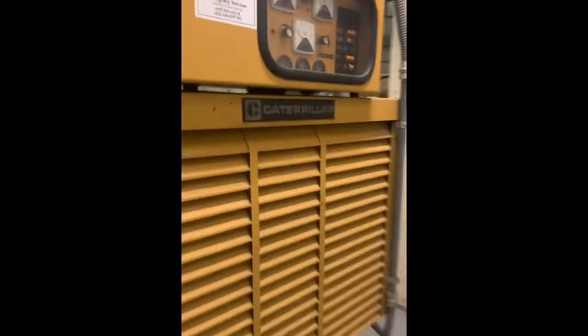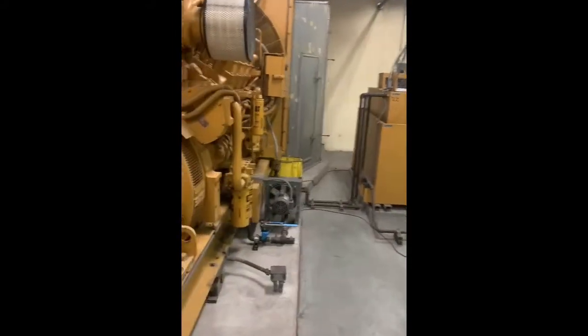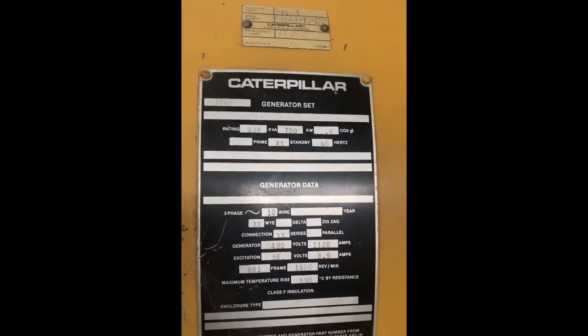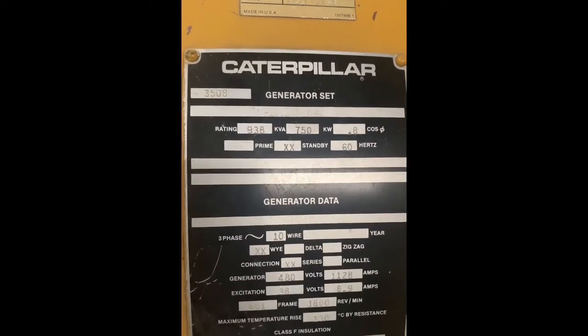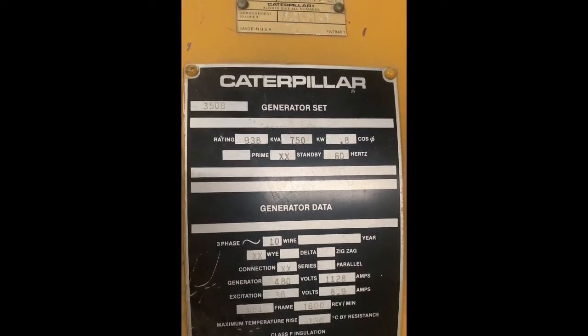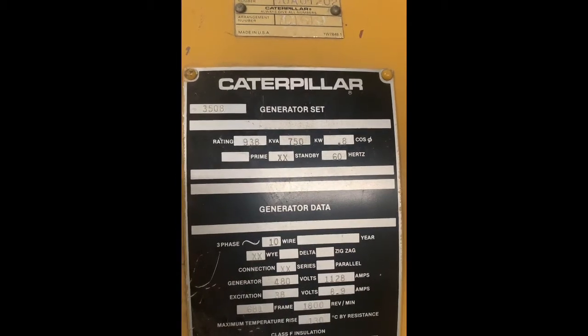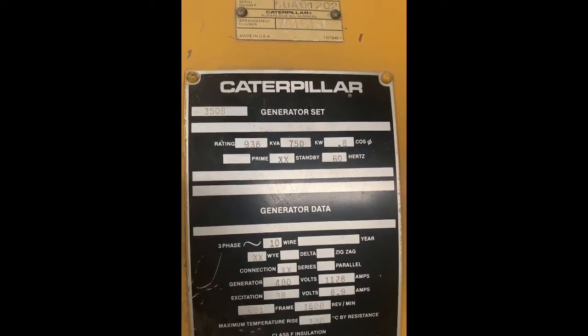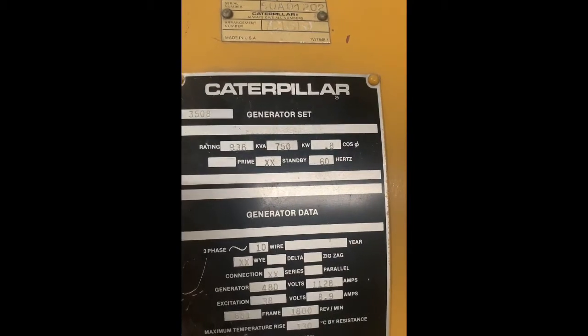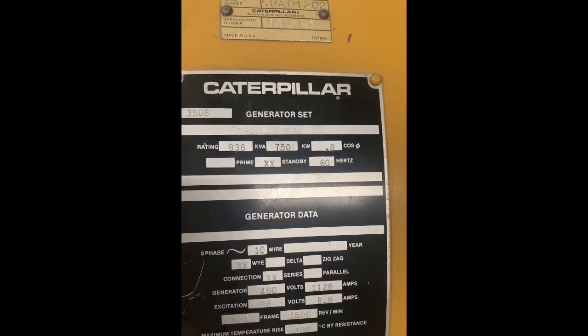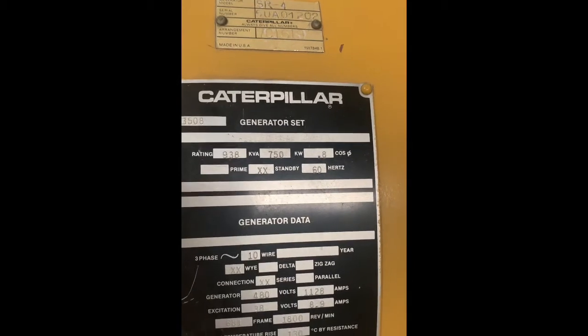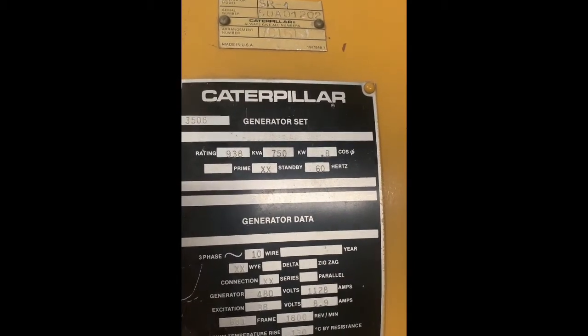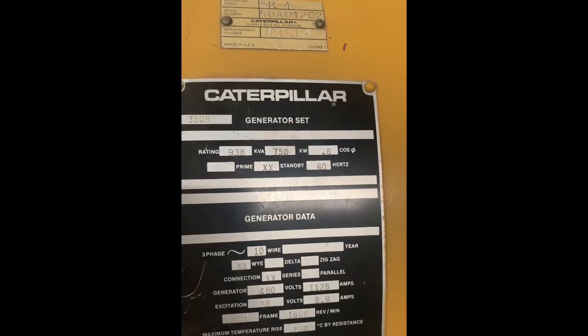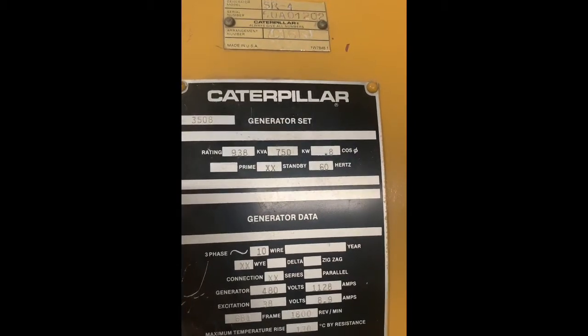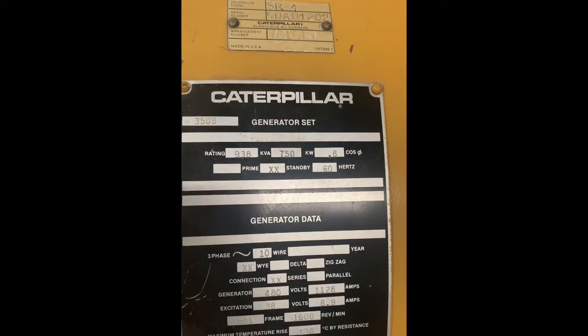Okay, this particular generator, go around to the nameplate, gives us all pertinent information. 938 kVA, which is basically kilovolts times amps, or watts in general. So it gives you the maximum it would be able to output, and then of course you need to multiply that by about 80% due to power factor to give you your wattage.